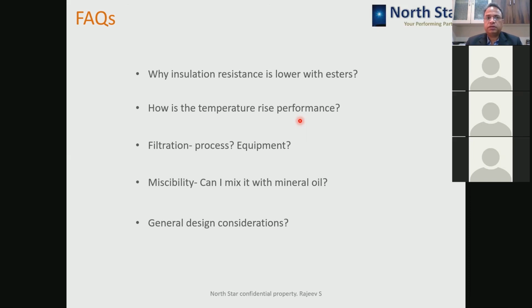But if you look at the standards, especially for example IS 2026 for transformers, nowhere are the acceptable limits for insulation resistance mentioned, because for all insulation properties like insulation resistance or tan delta or other such parameters, you cannot have one fixed value as a reference. With the type of material, the nature of the material changes, and for them these values will also change. So low insulation resistance is the property of the ester, so there is nothing to worry about if you are getting low insulation resistance.